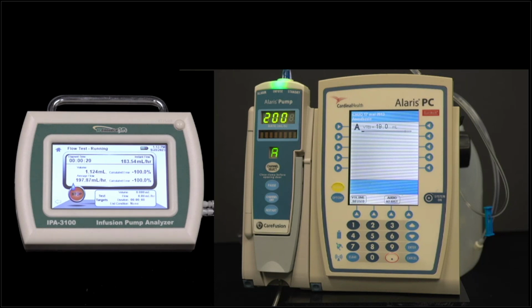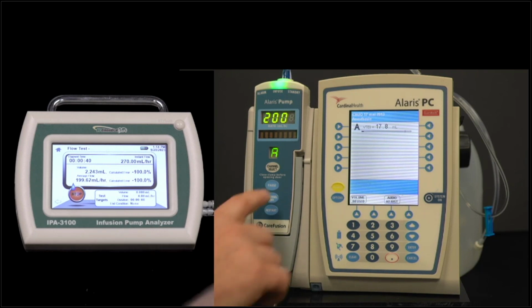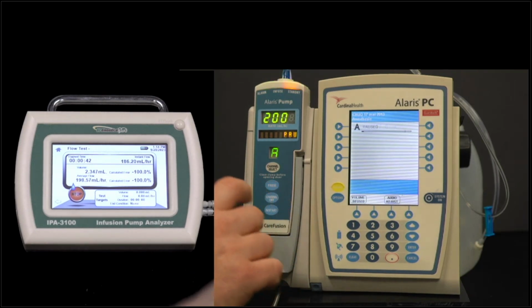Now it shows us the settings at the bottom, and we'll see that I had 0 set for everything, but that's okay, because for this test, I just want measurements. I just want to measure the function of this pump and see how it's working. So we'll see that the calculated error is minus 100%, and it stays there. So if I want to just quickly run a test and get measurements, that's a quick way to do it. I don't have to worry about those settings. I'm going to go ahead and pause the pump here.